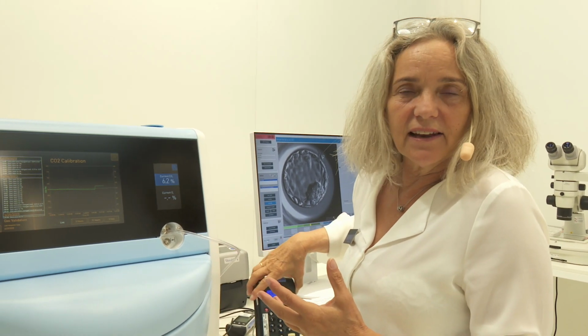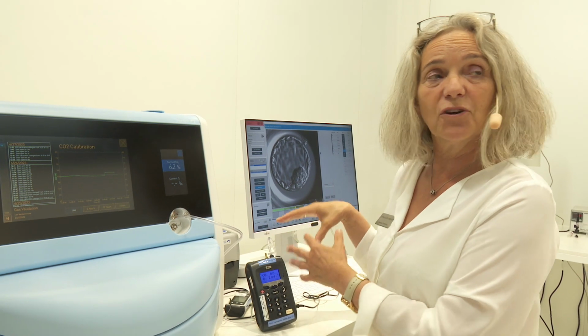Even though a gas analyzer is calibrated, there is a little bit of deviation from one instrument to another, so you must expect sometimes there is a natural deviation of 0.1, 0.2. So I will never calibrate the machine when it's only deviating 0.2. If it's deviating more than plus or minus 0.3, then you should contact our support team for advice, because this is not normal. It's very, very stable actually. But I would do it if it deviates 0.3.